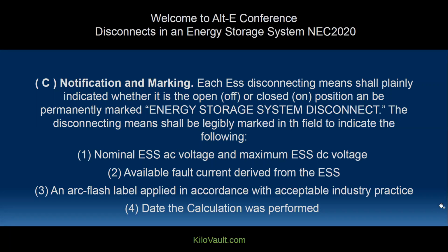Just one other question. Is there a DC amperage limitation? That's more the size of your system between the inverter and your energy storage at that point. What that disconnect needs to be rated at that time. That's more of just sizing and the design of the system at that point.